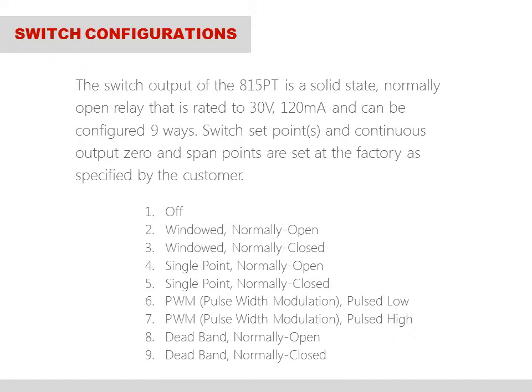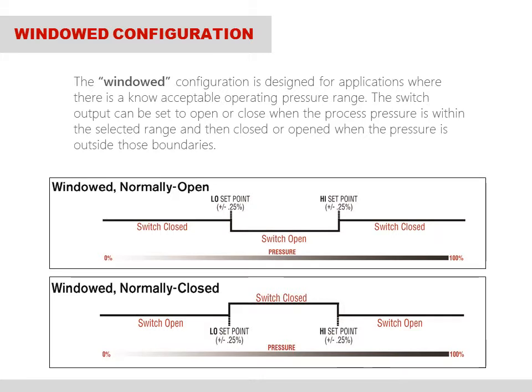PWM and deadband functionality enables the customer to address other unique applications. To better understand the windowed functionality of the 815 PT's switch output, consider the following example of the windowed, normally closed option, or the lower diagram. In this mode, the switch output is closed when the process pressure is within a user selectable range and open when the pressure is outside of these boundaries.